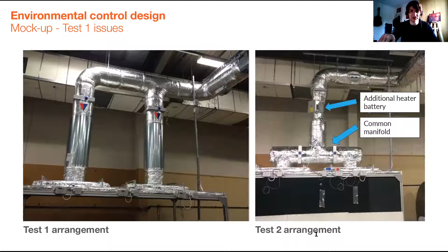So basically we modified the duct arrangement so that the main single duct gave maximum time for the air to mix before we separated it out to the two grills. Those were all the changes we made on the mock-up, and then we did some more tests, and we did see a real improvement.